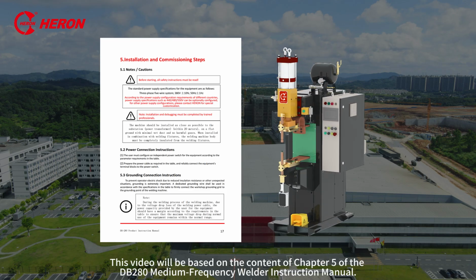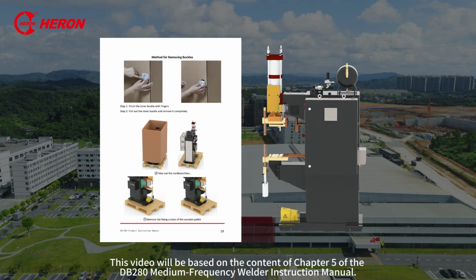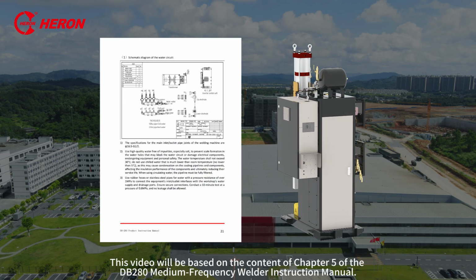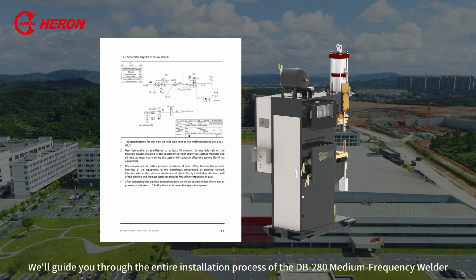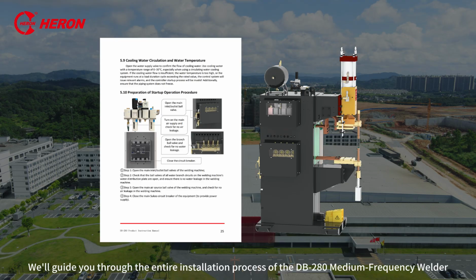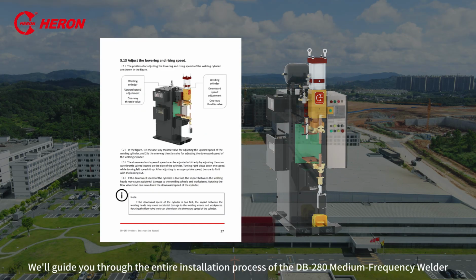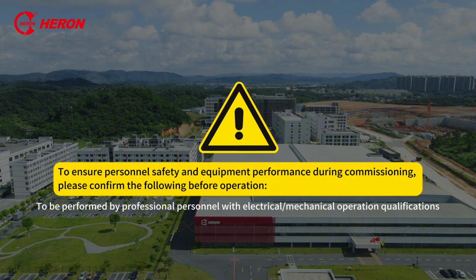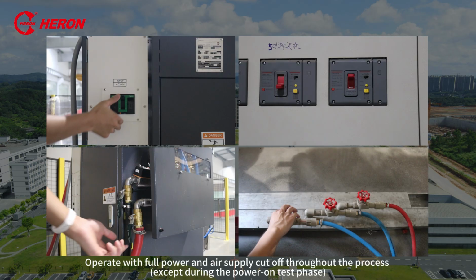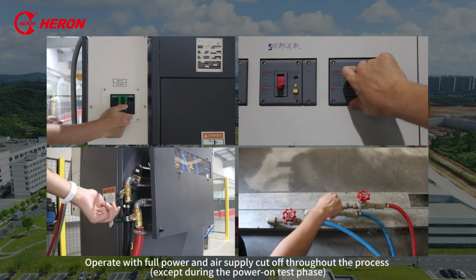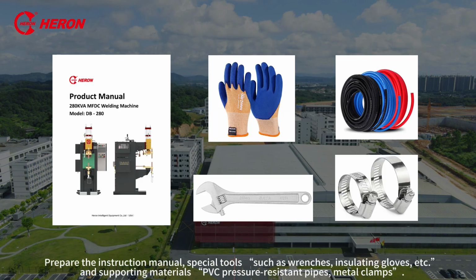This video will be based on the content of Chapter 5 of the DB-280 Medium-Frequency Welder Instruction Manual. We'll guide you through the entire installation process of the DB-280 Medium-Frequency Welder, to be performed by professional personnel with electrical and mechanical operation qualifications. Operate with full power and air supply cut-off throughout the process. Prepare the instruction manual, special tools such as wrenches, insulating gloves, etc., and supporting materials, PVC pressure-resistant pipes, metal clamps.